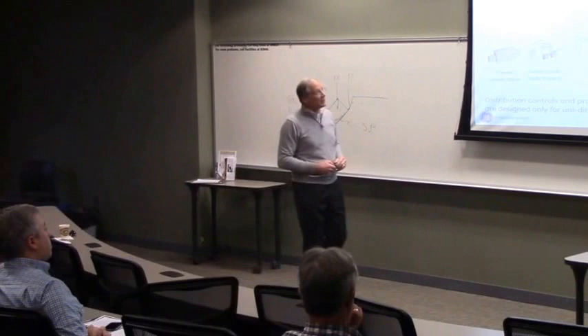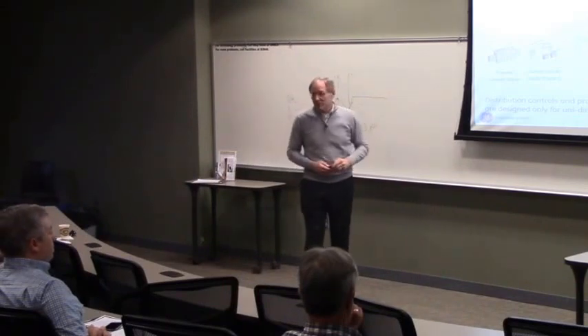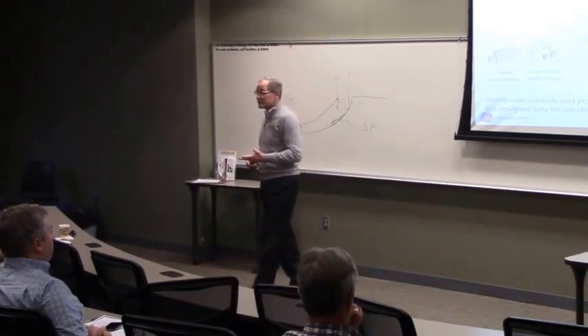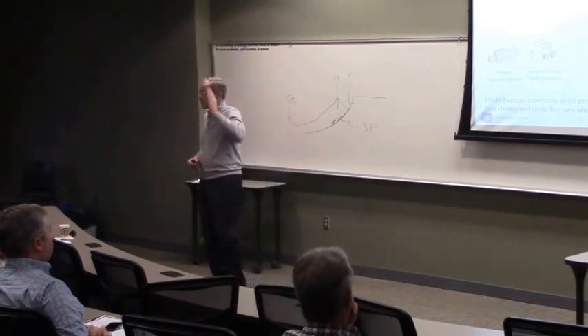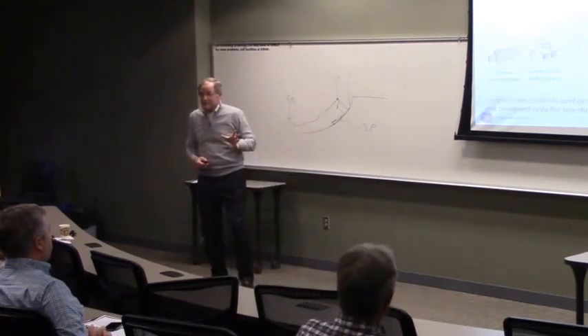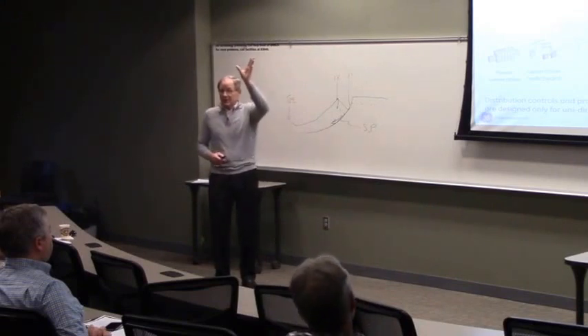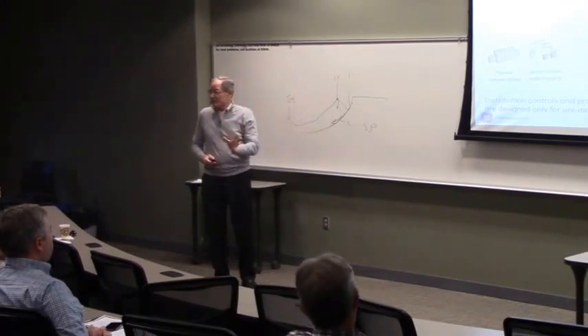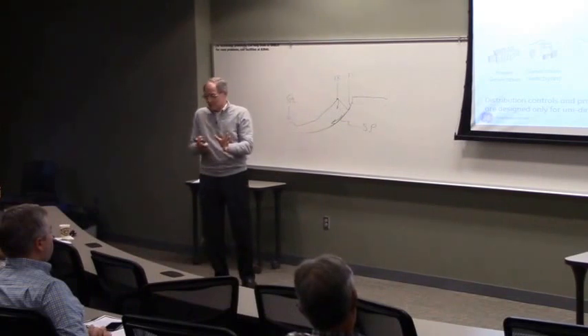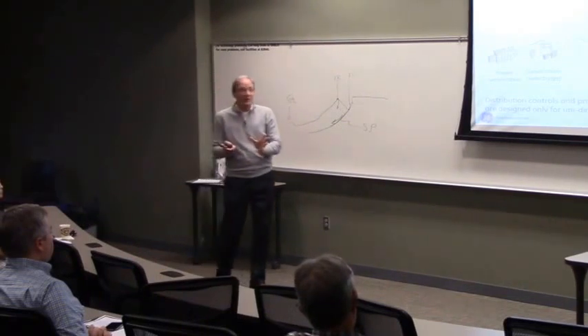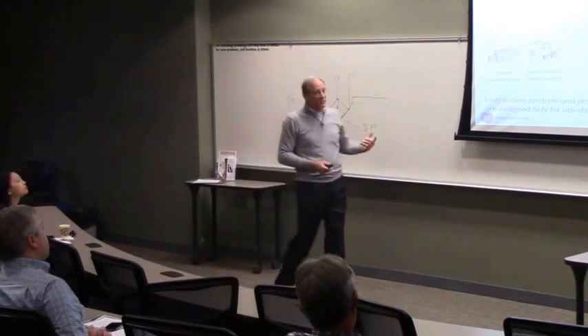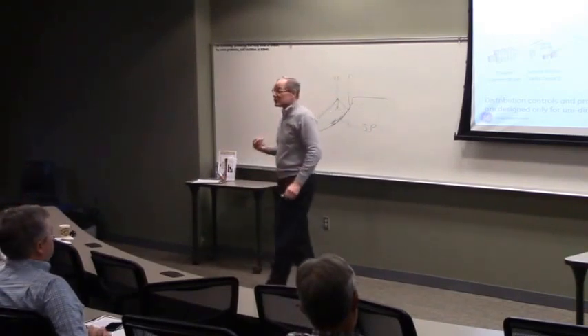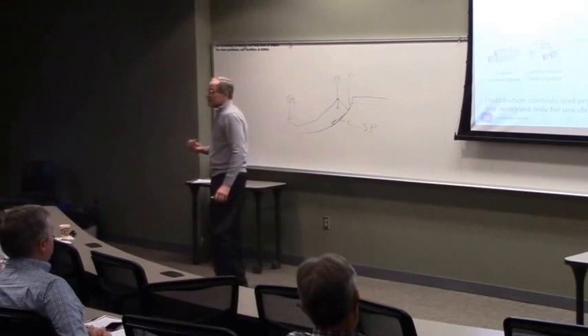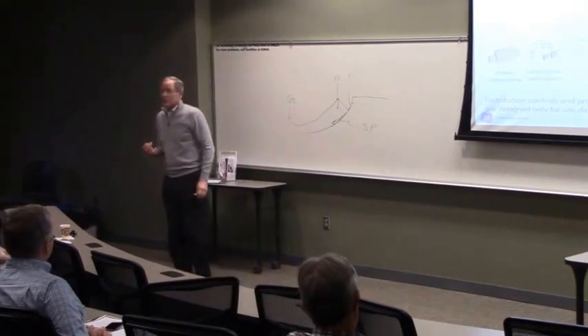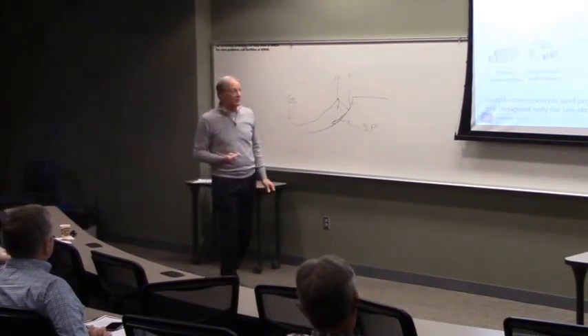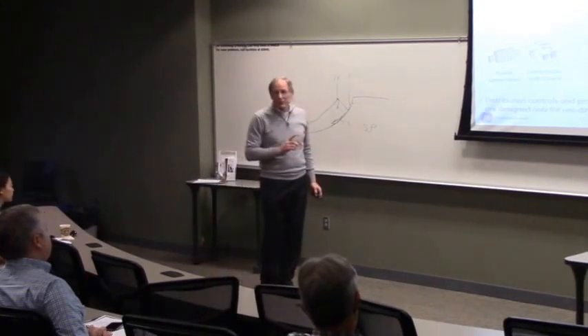But the thing we take into account is that the distribution system was designed for what? Electricity flowing in one direction, from source to load. Typically it's radial in architecture, so the feeder comes from the substation down to the last customer and stops. There's no tie point to another feeder in the substation. And the protection settings were done based on short circuit studies that looked at the source side contribution to the fault only, right? There was no load side contribution. Okay. But power flowing in one direction.